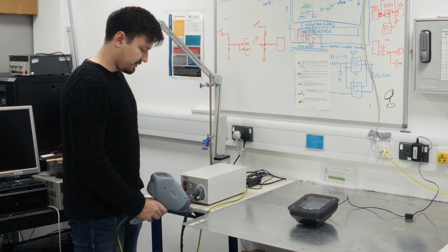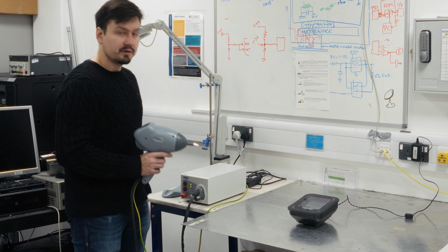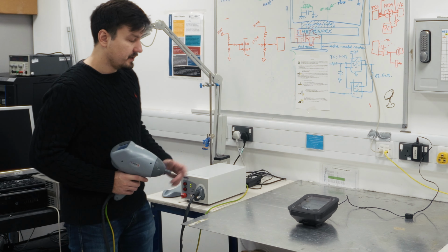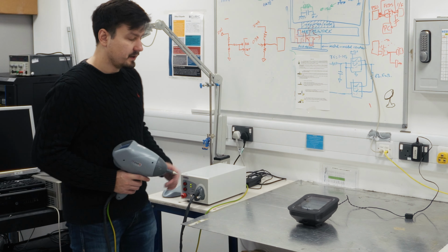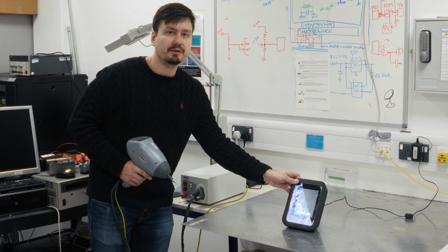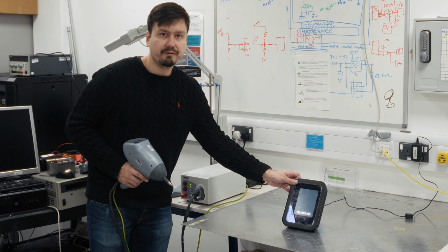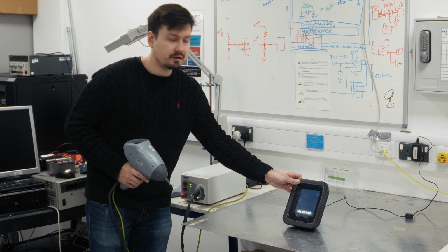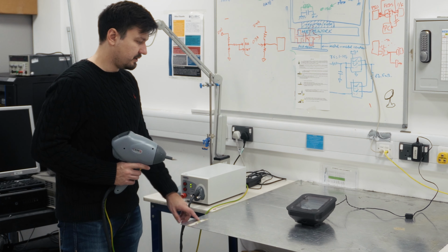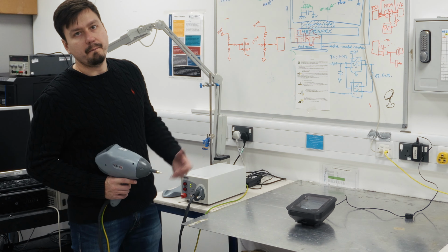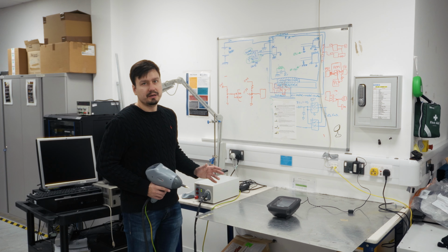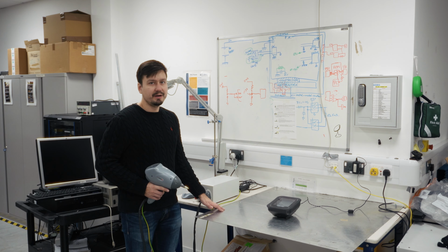Yeah, you probably can't hear it, but it is discharging. As you can see, the device is not affected. Maybe you cannot see, but you can see when I tip it over that the device is not affected by the discharge into the coupling plane, which is a good sign. And it is also discharging, which means that the device is actually coupling into the main screen. So at first we apply X amount of pulses as prescribed by the standard into the coupling plane. If you have a vertical coupling plane, you will do the same.